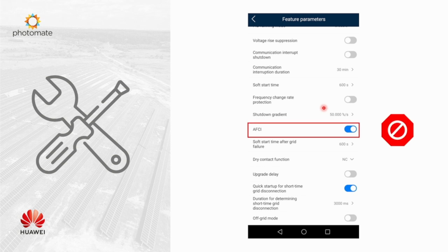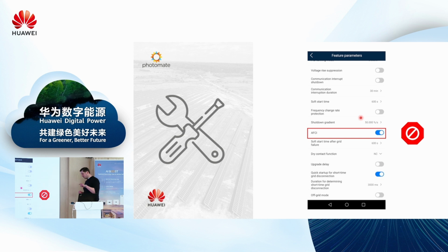And this is one of the most important functions I want to tell you about regarding safety. This is the AFCI function we talk about today. How does it work in detail? The inverter is detecting the arcing, and if it happens 5 times per day, the inverter will block itself and will not allow you to clear this alarm remotely, but you have to go on site, find the issue, repair it, and then clear the alarms locally and start up the inverter again. So this is because of safety reasons. The AFCI function right now has 100% accuracy, so it means if you have this alarm triggered, you have a problem on the PV side. It's not the fault of the inverter.